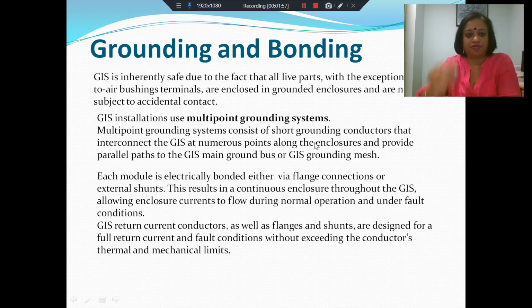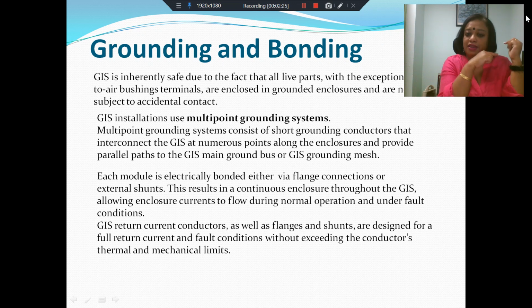Each module is electrically bonded. There are different modules, and each of these modules is a standalone prefabricated unit, and they are connected end to end either through flange connections or through external shunts. So this is like a continuous enclosure. After the connection, all these modules connect as a single enclosure. Therefore, if you have any currents flowing through the enclosure path, they will flow through the entire enclosure path. So we have the possibility of enclosure currents flowing during normal operation as well as under fault conditions.